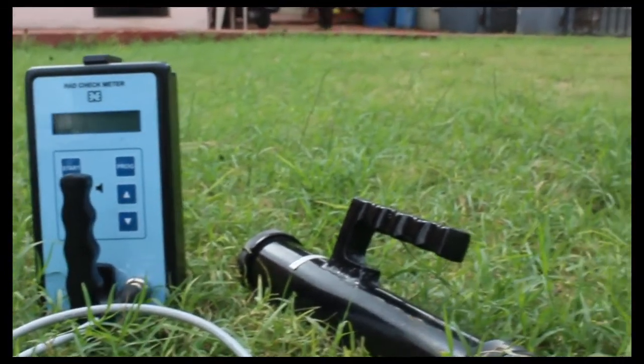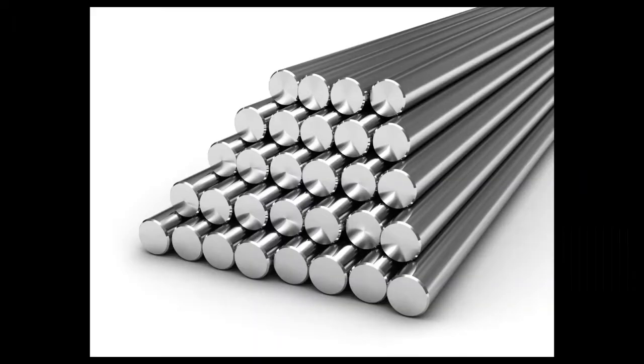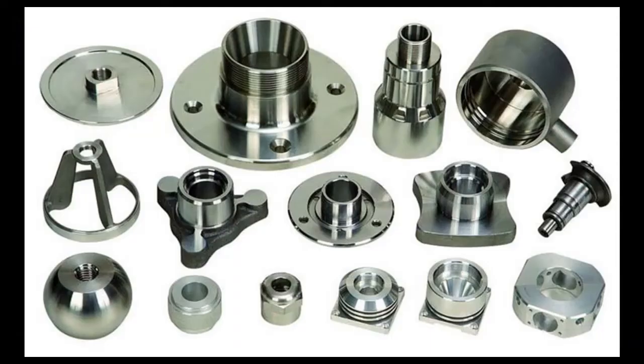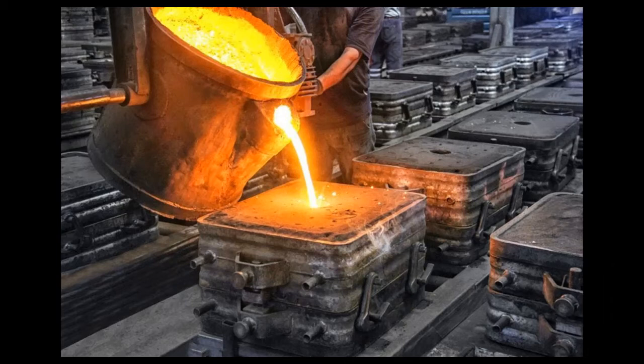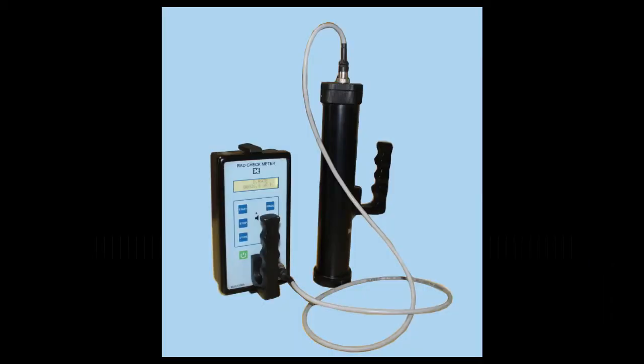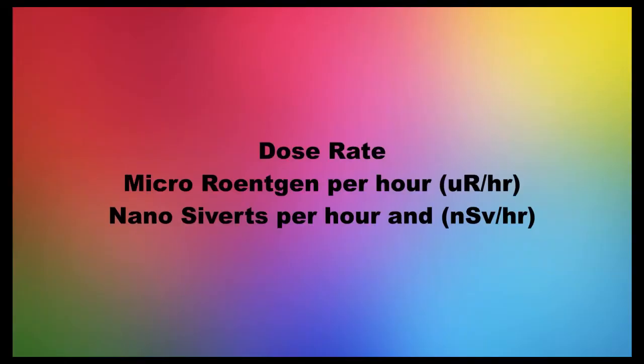It is used to measure radioactive contamination in bars, billets, rods, engineering components, and castings manufactured by metal industry. It basically measures radioactive contamination by indicating dose rate in microroentgen per hour and nanosieverts per hour.